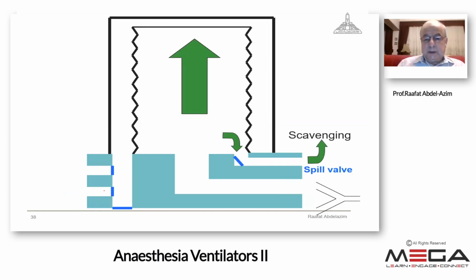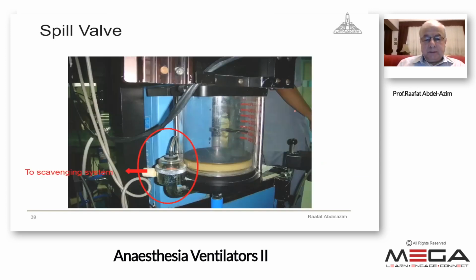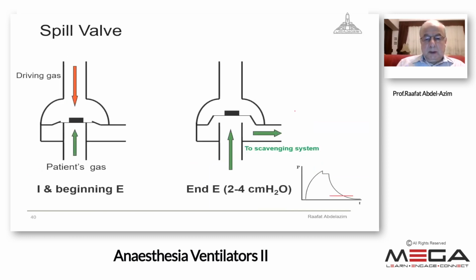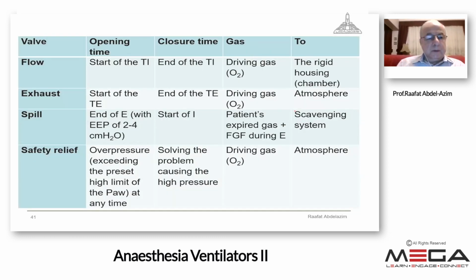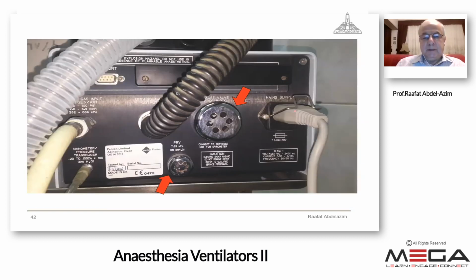Near the end of expiration, when the bellows is coming up, the spill valve will open to vent the excess patient gas that contains anesthetic, carbon dioxide, and water vapor. This will be vented into the scavenging system to prevent pollution. The spill valve. This is a summary of the 4 valves that operate the ventilator, what time they open, what time they close, what is the gas coming through it, and where is the fate of this gas.